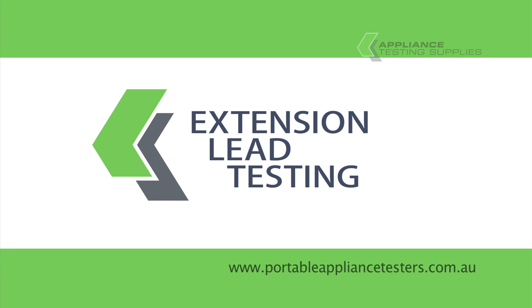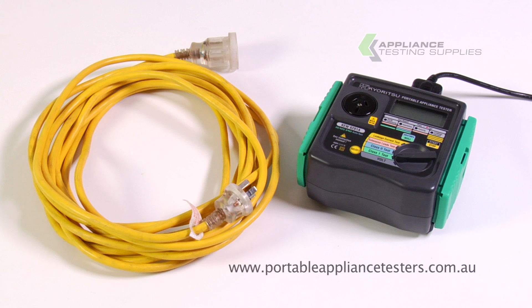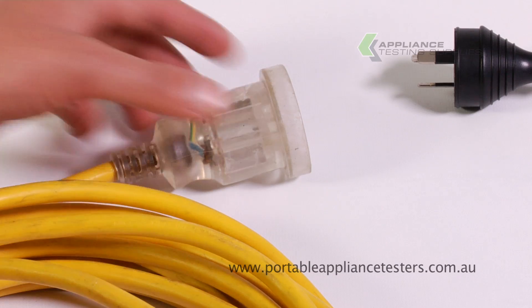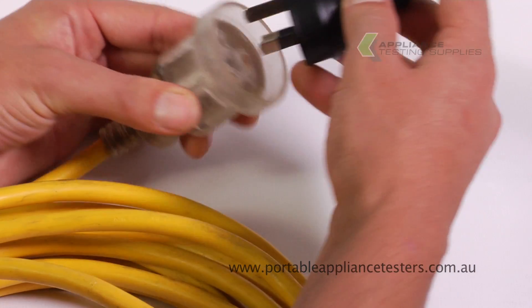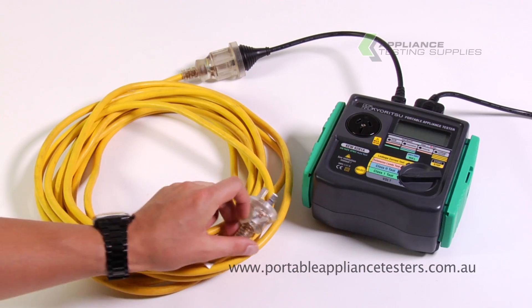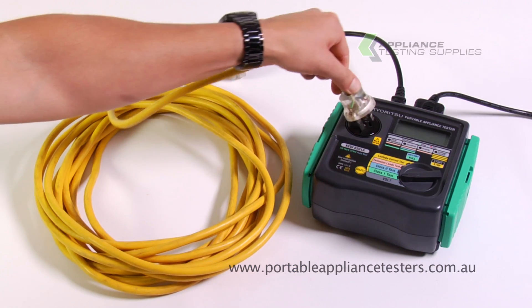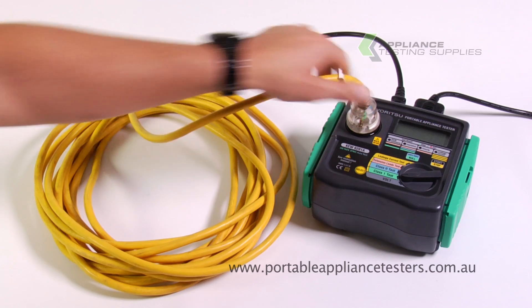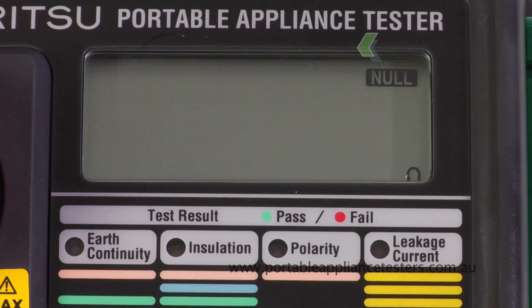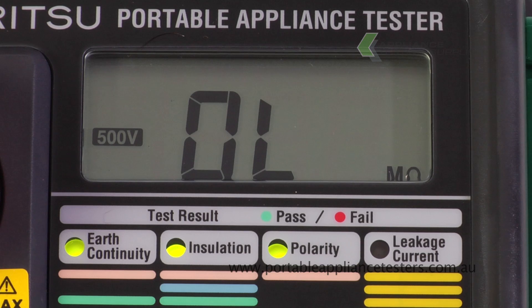Testing extension leads. Using the extension lead adapter provided, plug it into the top of the appliance tester. Plug the other end into the extension lead. And to create the circuit, plug the extension lead into the front of the Kyoritsu. Turn the dial to an extension lead test and press start to continue. This unit will now conduct an earth continuity, an insulation resistance and a polarity test. The results will appear on the screen with a green LED light for pass, red for fail.